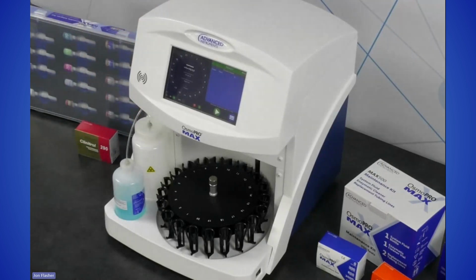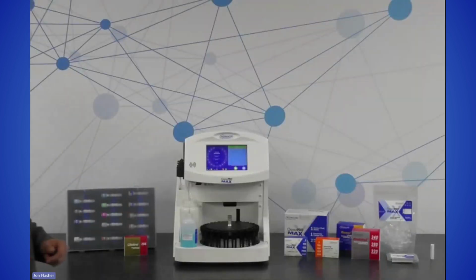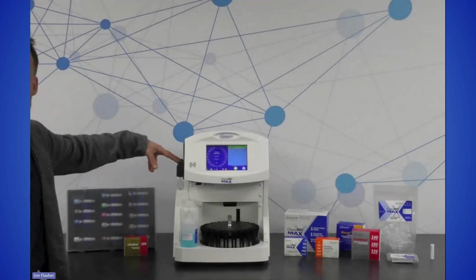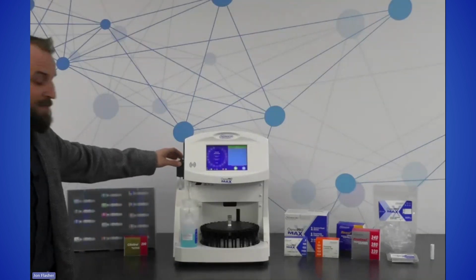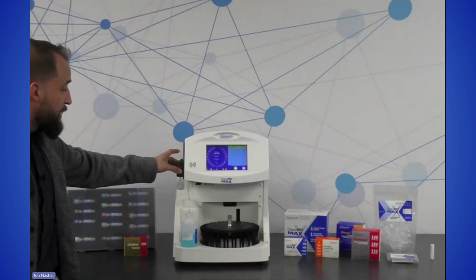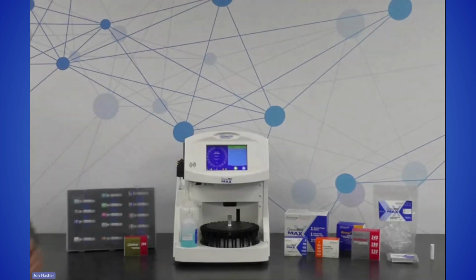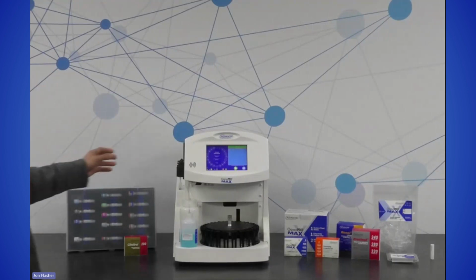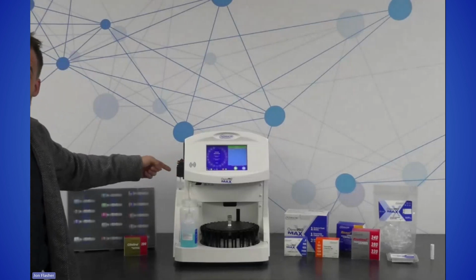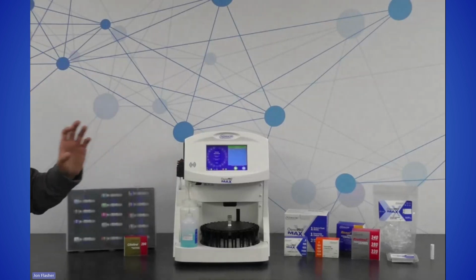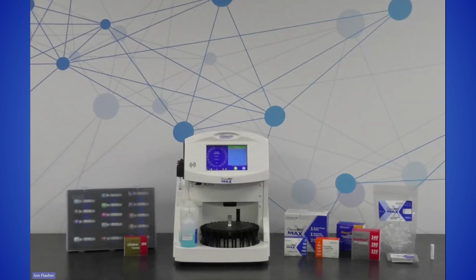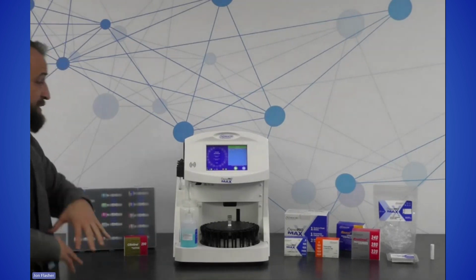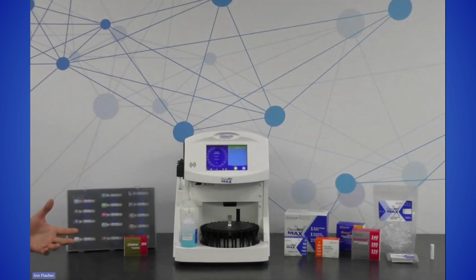Over here on the side of the instrument, we're going to switch camera angles again. We'll see how handy I am with this. You'll see these two little black things here, and those are our pump tubing housing. The peristaltic pump, which actually drives the movement of the fluid through the fluidic pathway, lives within this housing. And there are little tubes that clip into place under this housing that need to be replaced every 500 tests as part of the regular maintenance of the instrument. We'll get into that very shortly. But that's really, at face value, everything you can see of the OsmoPRO MAX.